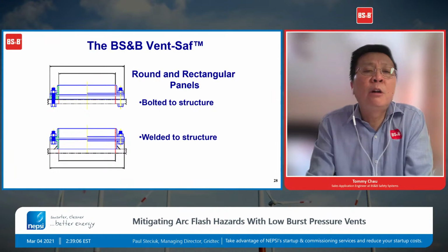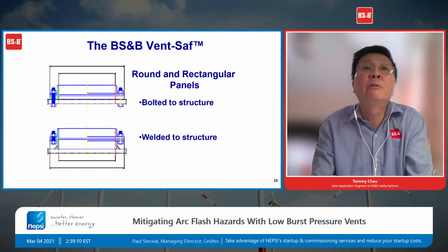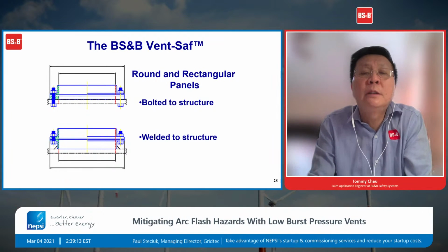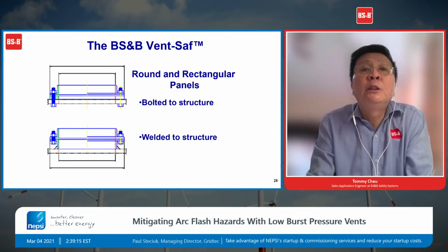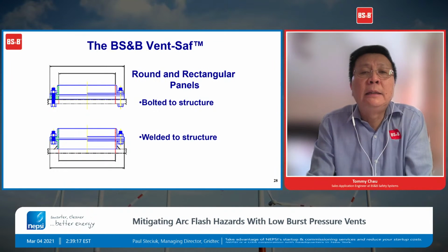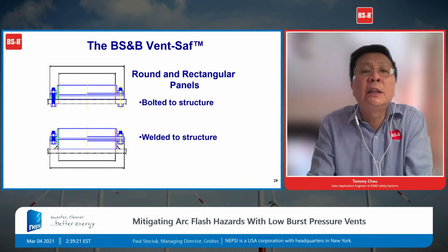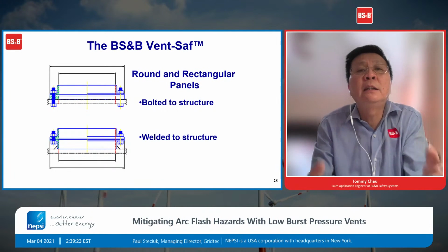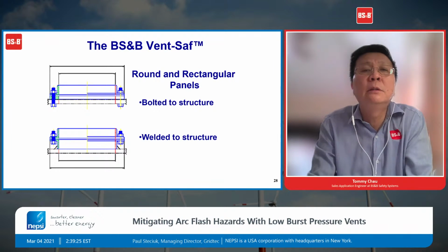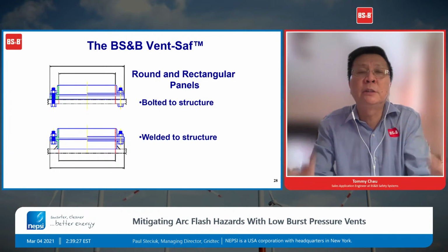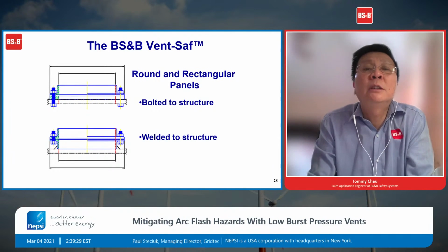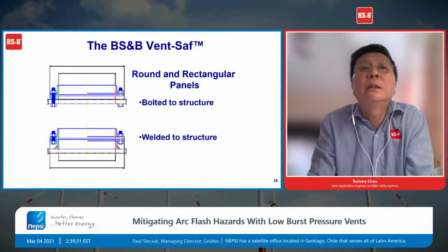BS&B also provide a safety frame, which is used with the explosion vent. Typically, you have to have a flange that's connected to your opening on the equipment and the explosion vent, and then you have a hold down piece that bolts the whole assembly together. So we provide either a welded type or the bolted type safety frame.